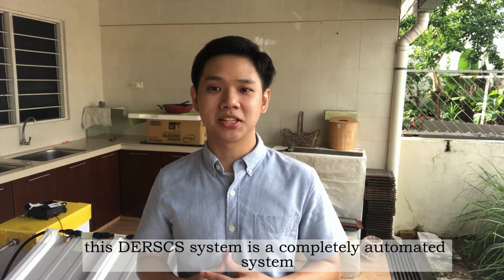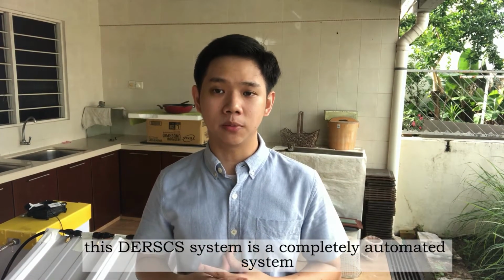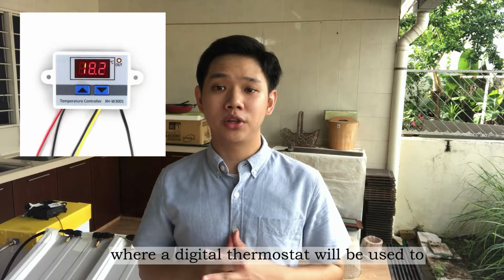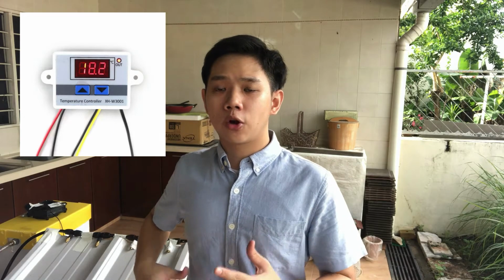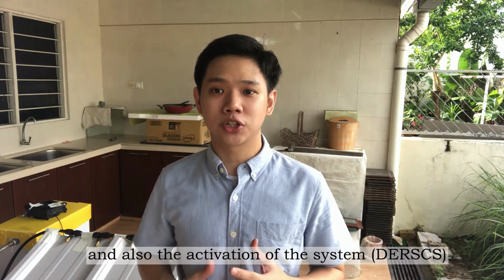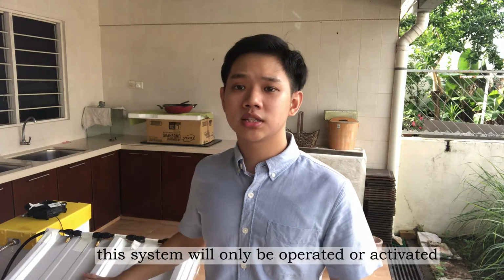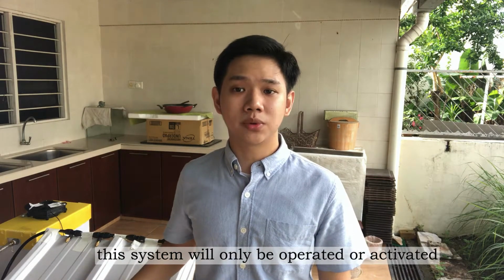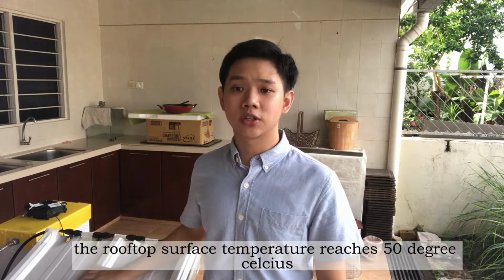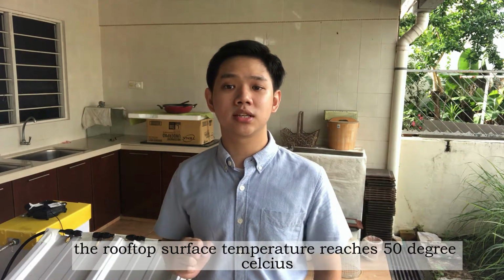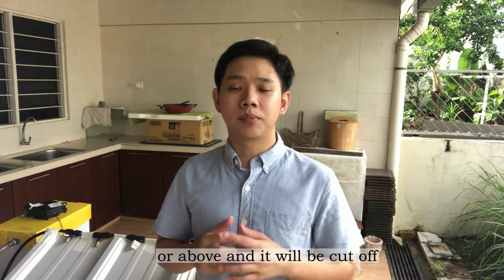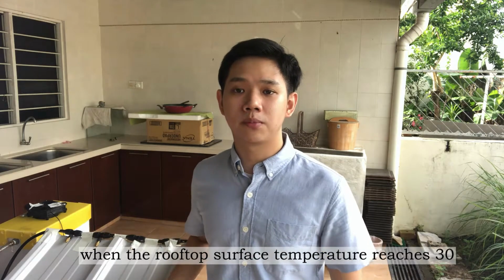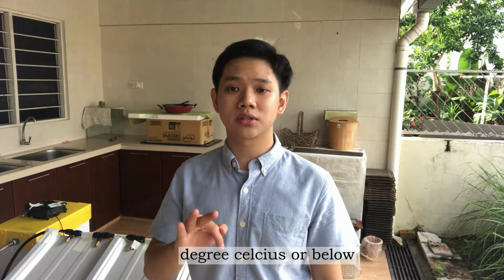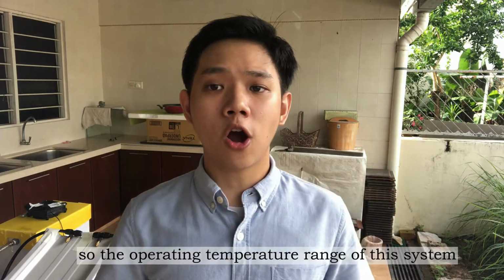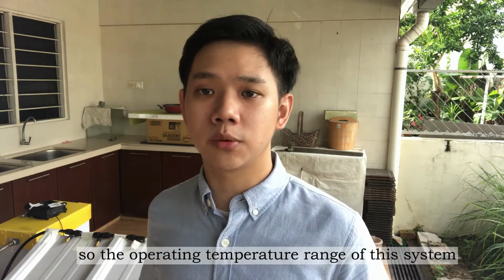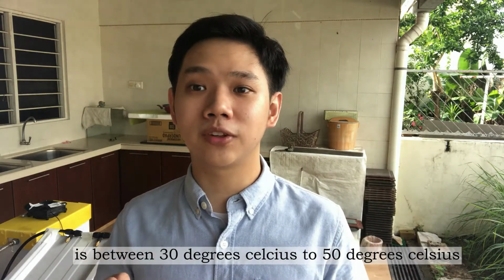This DERSCS system is a completely automated system where a digital thermostat controls the operation and activation of the system. It only operates when the rooftop surface temperature reaches 50 degrees Celsius or above, and is cut off when it reaches 30 degrees Celsius or below. So the operating temperature range of this system is between 30 and 50 degrees Celsius.